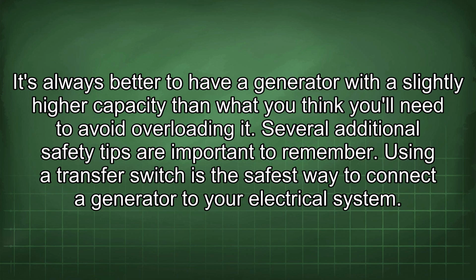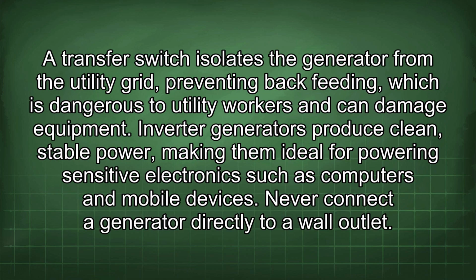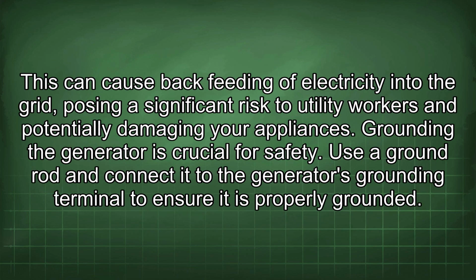Using a transfer switch is the safest way to connect a generator to your electrical system. A transfer switch isolates the generator from the utility grid, preventing backfeeding, which is dangerous to utility workers and can damage equipment. Inverter generators produce clean, stable power, making them ideal for powering sensitive electronics such as computers and mobile devices. Never connect a generator directly to a wall outlet. This can cause backfeeding of electricity into the grid, posing a significant risk to utility workers and potentially damaging your appliances. Grounding the generator is crucial for safety. Use a ground rod and connect it to the generator's grounding terminal to ensure it is properly grounded.